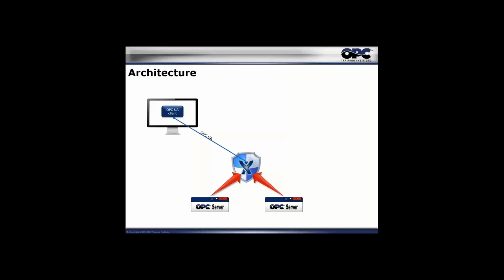Now, the architecture is pretty simple. It works like this. The OPC servers are connected to the gateway, of course via OPC or whatever you happen to use. Now, from there, we send information to the OPC UA client. So this is a third-party OPC UA client. It might come to this gateway via OPC UA. If you have an OPC DA client, you put it through another gateway over here, you effectively tunnel, and you go through OPC UA.